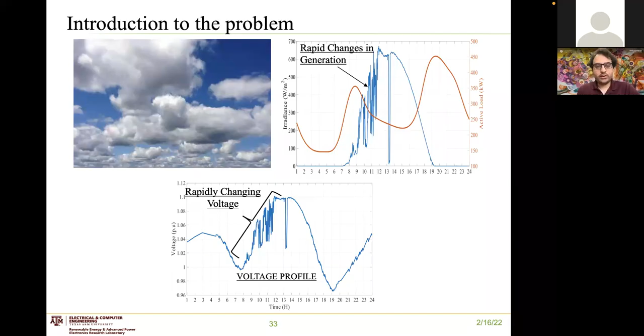We might have a situation where we have intermittent clouds. So we have lots of these clouds randomly moving and blocking the sunlight that's hitting the panel. In that case, we will have an irradiance profile that has these rapid changes. And if we were to calculate the power that's injected into the network from this PV system, the generation will also experience similar rapid changes. Now, the voltage at this point where our PV is connected to the network looks something like this, with rapidly changing voltage. Such a voltage profile can wreak havoc on our regulators and capacitor banks, since they are mechanical devices, and these changes happen in time scales of minutes or even seconds. So when you have enough distributed generation, and that means there is an increased likelihood of your voltages being highly variable, that will stretch these devices to the limits of their operation and hence cause accelerated wear and tear of these devices, and they might fail much earlier than they were designed for.